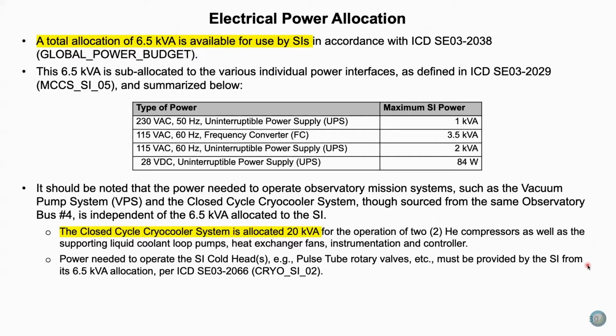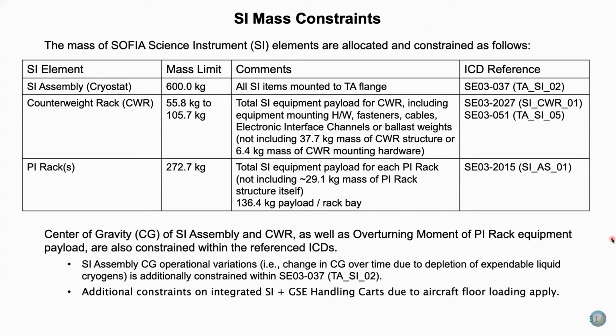Electrical power distribution, we don't need to talk about this. There's a 6.5 kVA allocation for the SI itself. And it's important to note that this does not include the compressors for the pulse tubes. Those have their own power source, 20 kVA power dedicated to them, to the both of them.